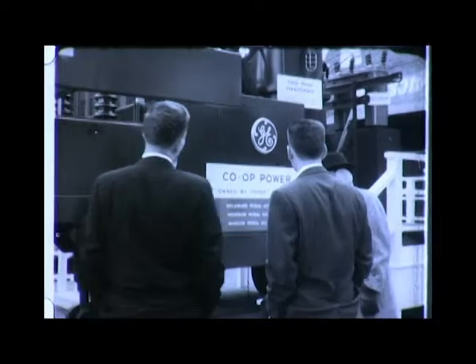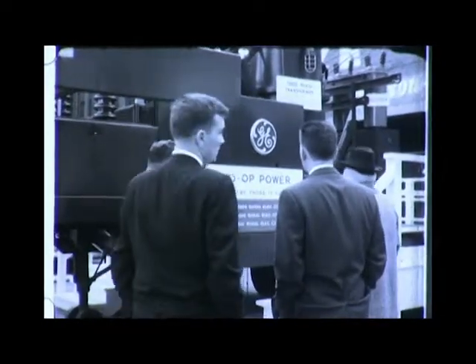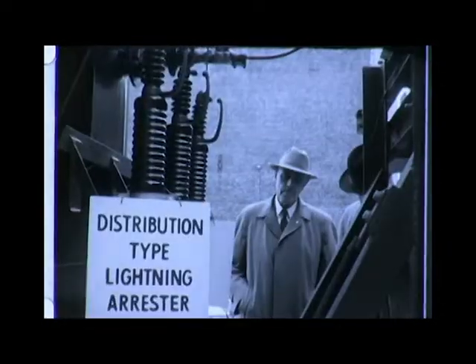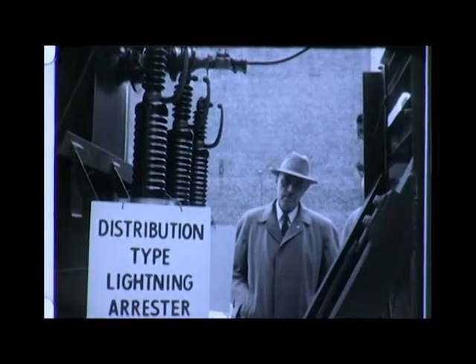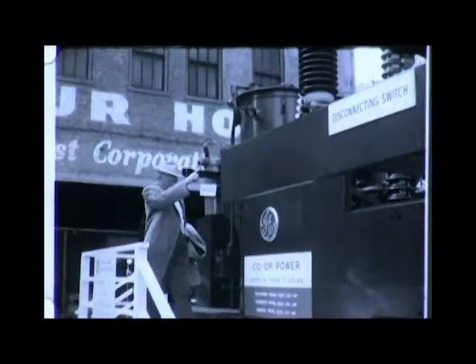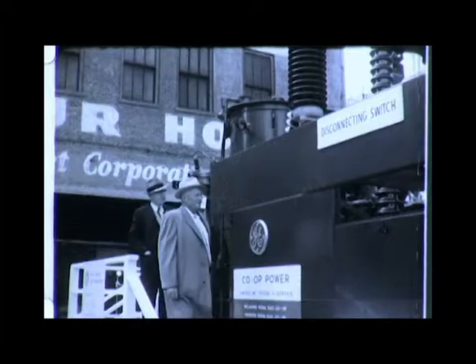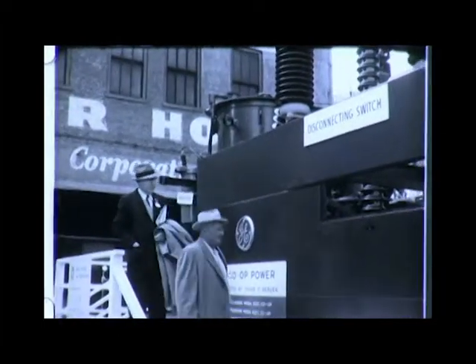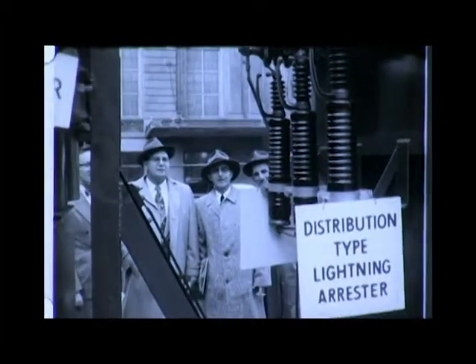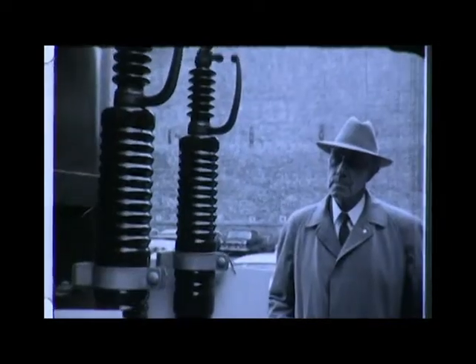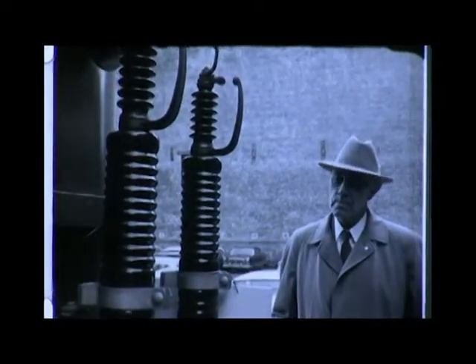Regrouping of existing single-phase transformers and combining spares and new substations with a mobile unit as reserve capacity can push savings to 5 figures. Or the three-phase RM transformer can save up to 1/3 of the price of 4 single-phase units. Smaller RECs may find a joint purchase advantageous.